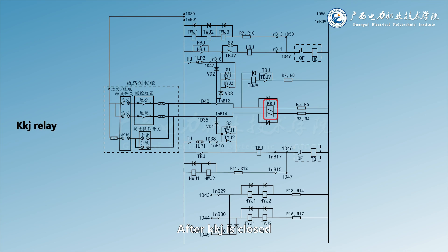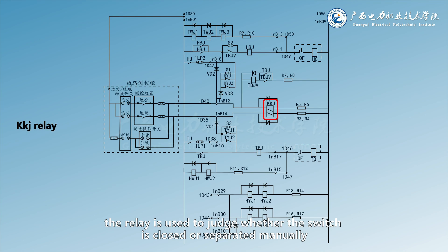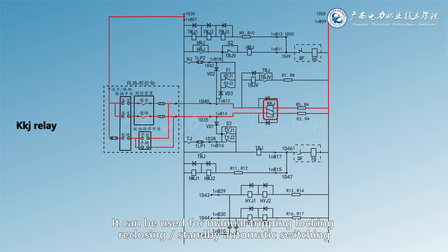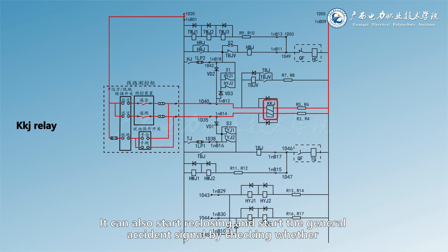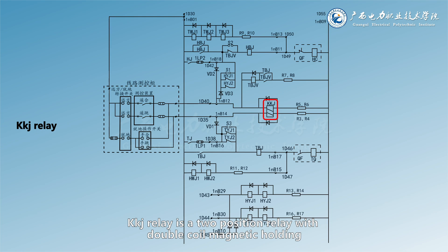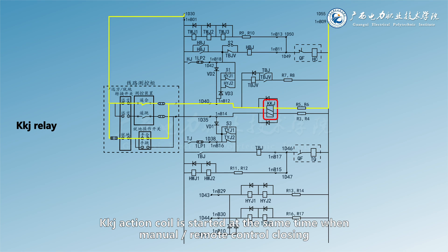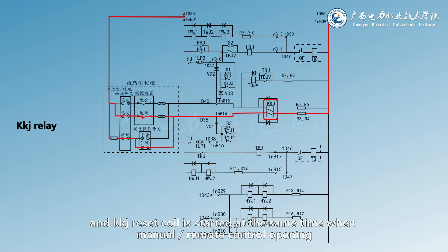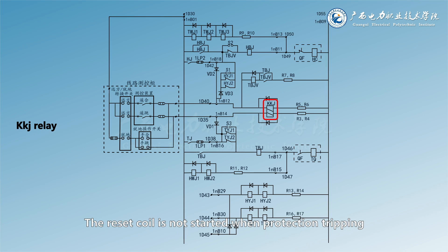After KKJ closes, the relay is used to judge whether the switch is manually closed or separated. It can be used for manual tripping locking, REC closing, and standby automatic switching. It can also start REC closing and start the general accident signal by checking whether the KKJ position contact corresponds to the actual position of the switch. KKJ relay is a two-position relay with double coil magnetic holding, having an action coil and a reset coil. The KKJ action coil is started at the same time as manual/remote control closing, and the KKJ reset coil is started at the same time as manual/remote control opening. The reset coil is not started when protection tripping occurs.